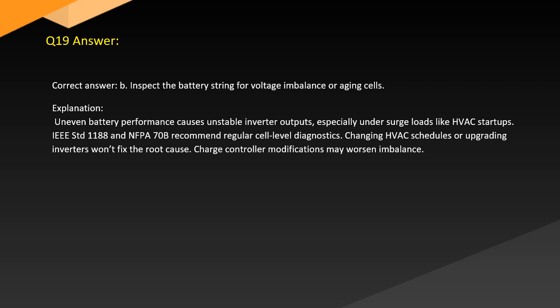Answer. Correct answer: B. Inspect the battery string for voltage imbalance or aging cells. Explanation. Uneven battery performance causes unstable inverter outputs, especially under surge loads like HVAC startups. IEEE Std 1188 and NFPA 70B recommend regular cell-level diagnostics. Changing HVAC schedules or upgrading inverters won't fix the root cause. Charge controller modifications may worsen imbalance.